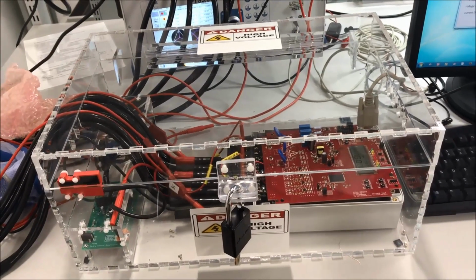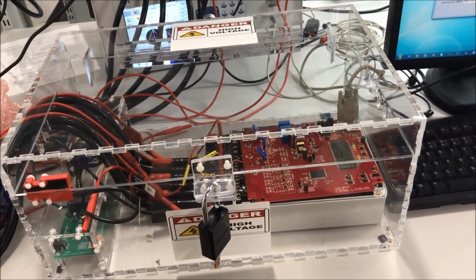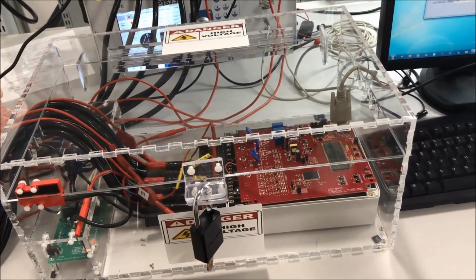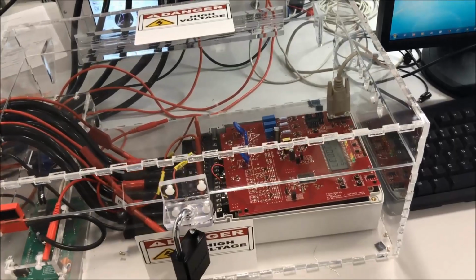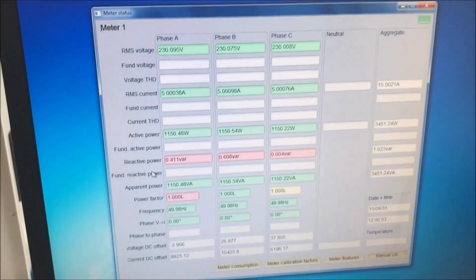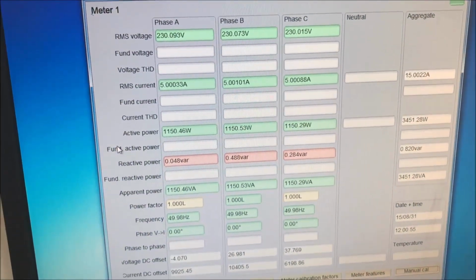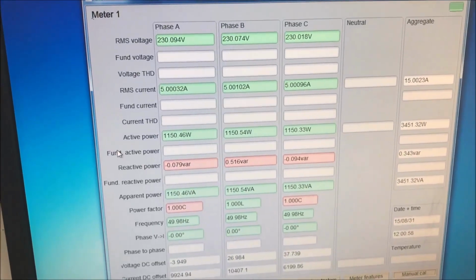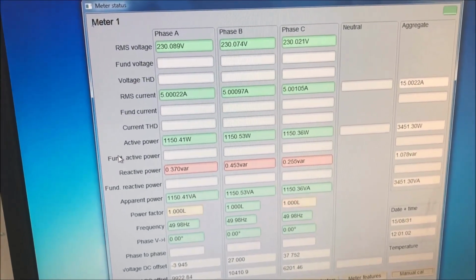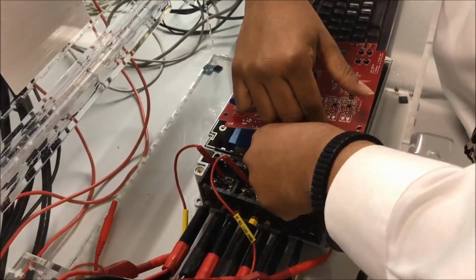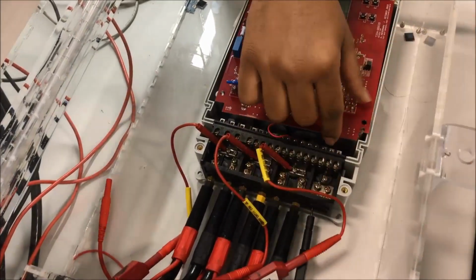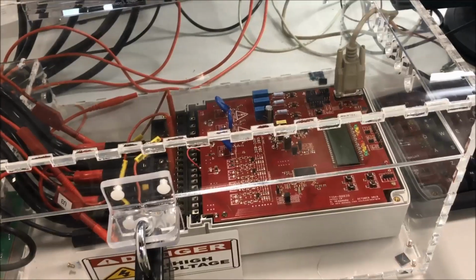To show the effect of magnetic tampering, we apply 230 volts, 5 amps, and unity power factor on each phase of the electricity meter. To show the effects of tampering, we use a PC GUI that will display the active power readings of each phase. Here we see that approximately 1150 watts has been applied to each individual phase. Now we'll see how some of these values would change when we apply a magnet on a particular CT. For this test, we applied the magnet on top of the CT for phase C. After applying the magnet, we then applied the same 230 volts, 5 amp, unity power factor conditions.